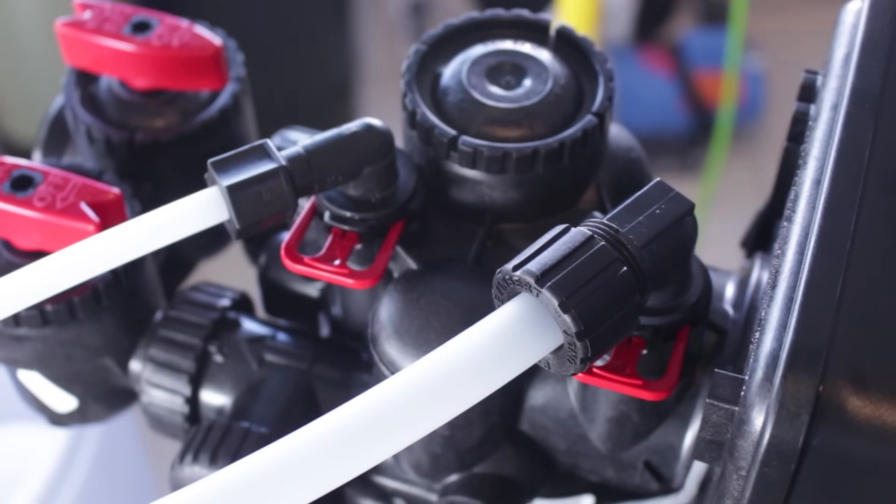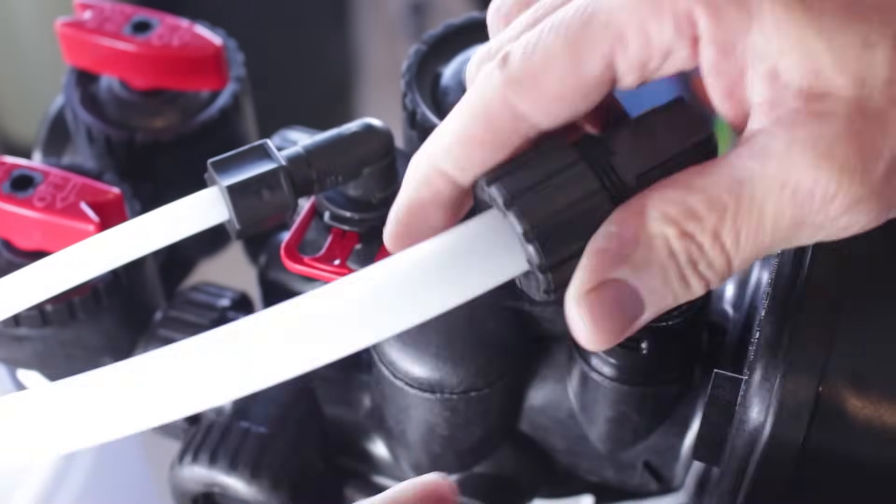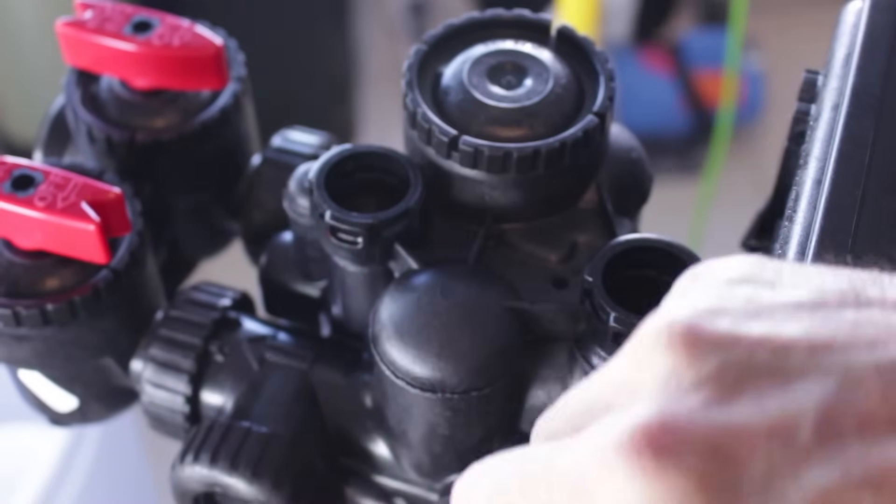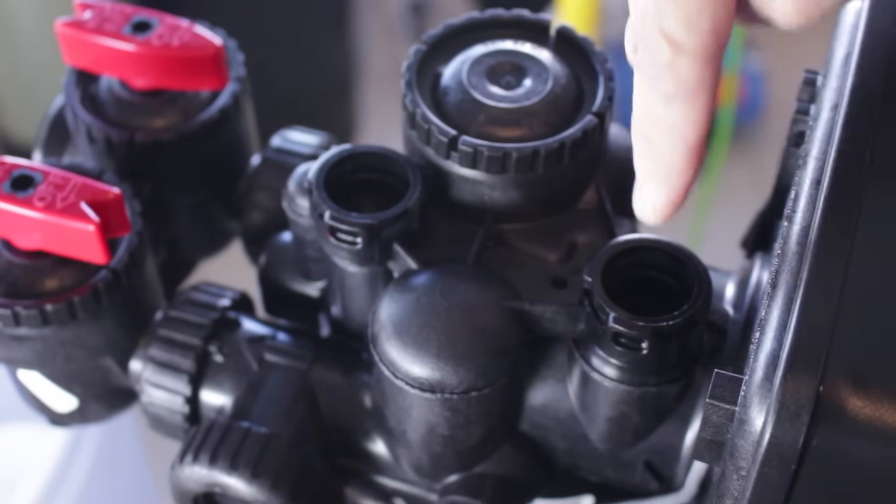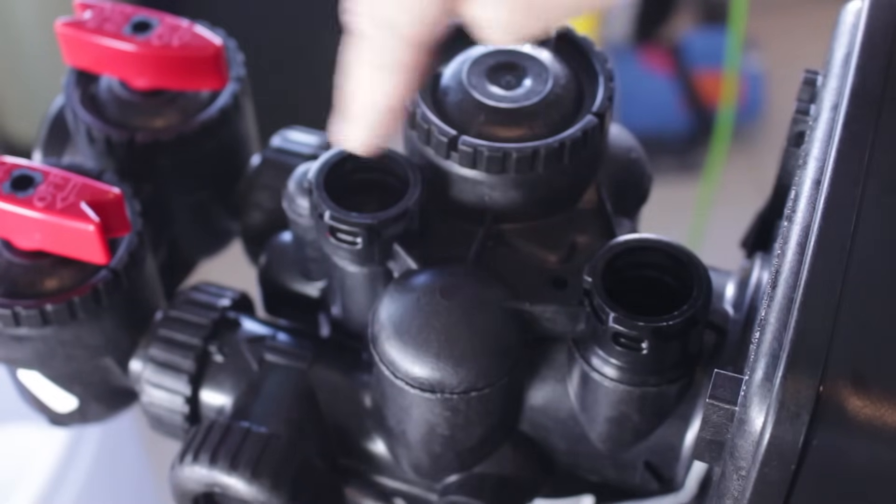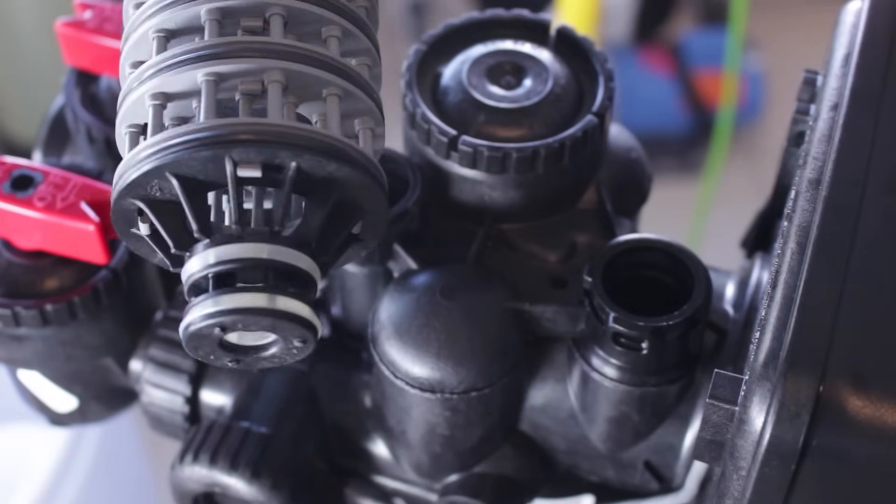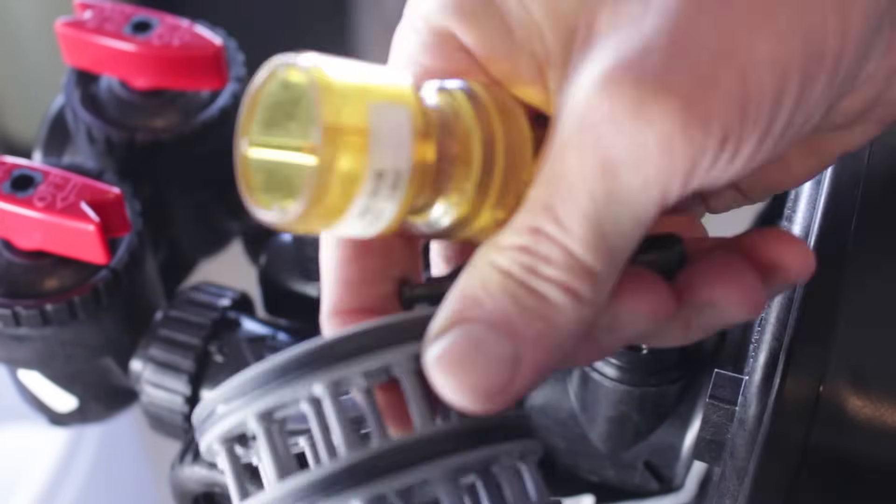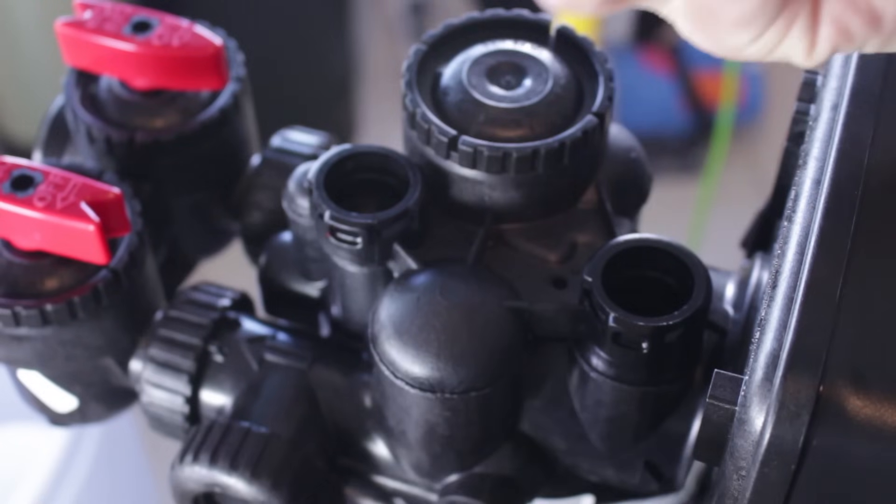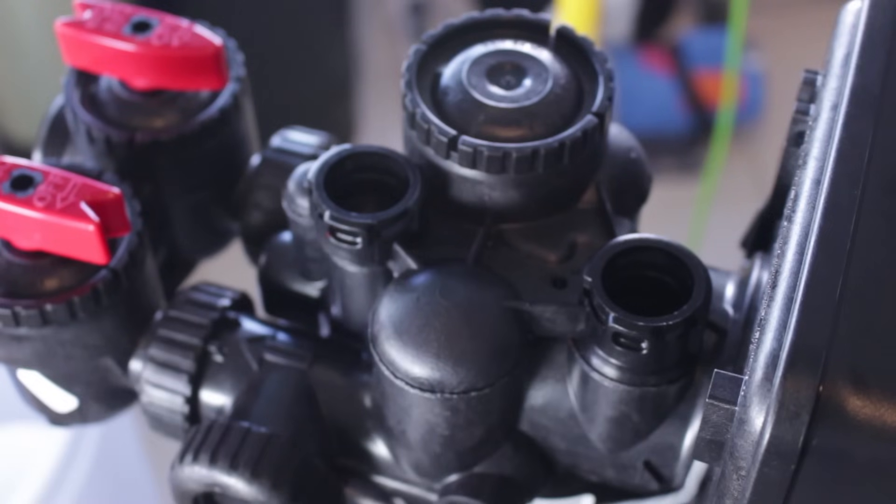The last thing to check is the spacer stack and pistons. To do that you would remove the drain line and the brine line, and with the valve in service you'd look down to see if there's any water flowing across the valve. If it was, then the problem is with the spacer stack and the pistons and they would need to be replaced. A spacer stack for this model water softener looks like this. Pistons look like these and it's a fairly large job to do it, but that would be the cure for this.